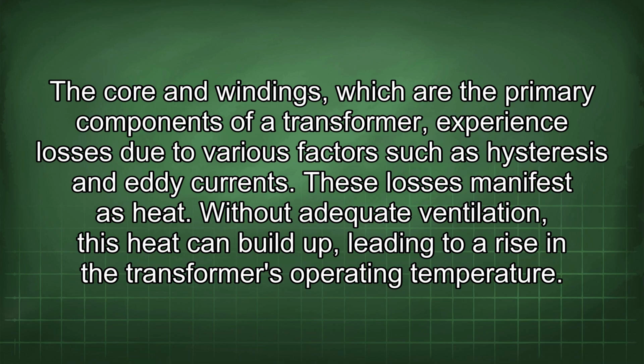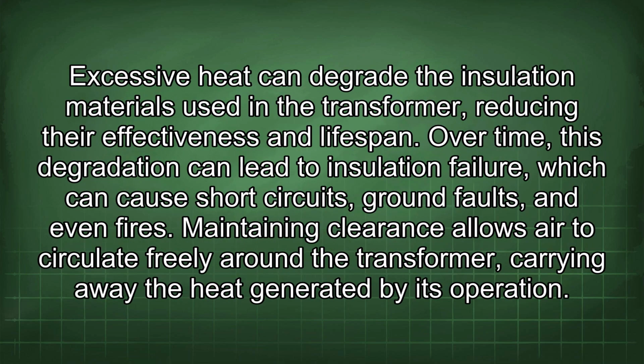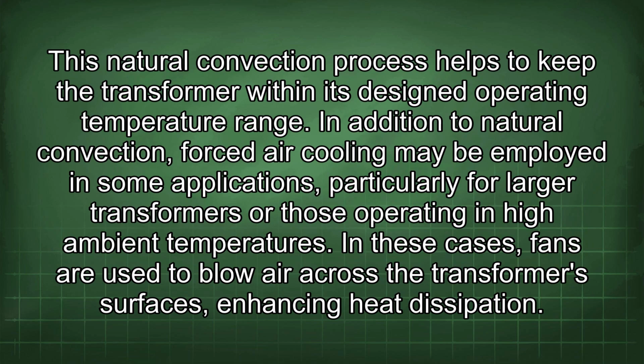Without adequate ventilation, this heat can build up, leading to a rise in the transformer's operating temperature. Excessive heat can degrade the insulation materials used in the transformer, reducing their effectiveness and lifespan. Over time, this degradation can lead to insulation failure, which can cause short circuits, ground faults, and even fires. Maintaining clearance allows air to circulate freely around the transformer, carrying away the heat generated by its operation. This natural convection process helps to keep the transformer within its designed operating temperature range.